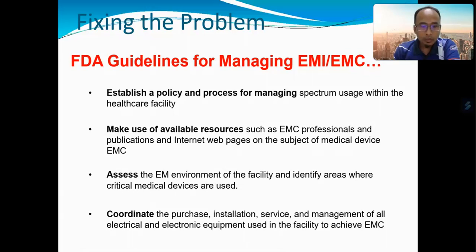All right. According to the Food and Drug Administration guidelines for managing EMI and EMC, there are a few guidelines that have been outlined. The first one, in order to manage EMI and EMC, we can establish a policy and process for managing spectrum usage within the healthcare facility.